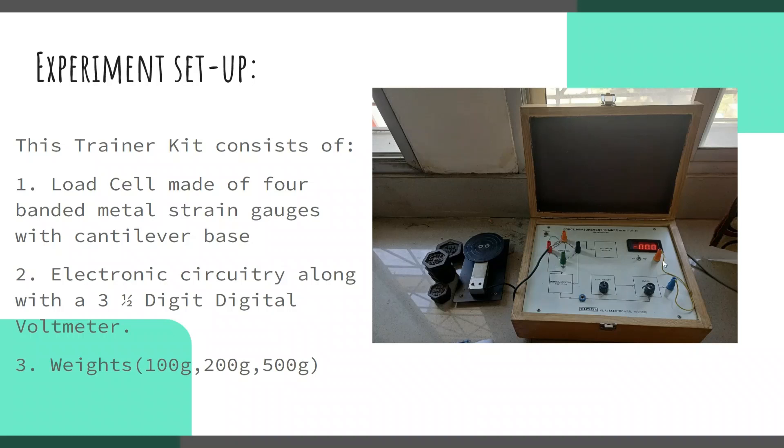Looking into the experimental setup, this is how our force measurement trainer model looks like. This model consists of an internal circuit which is composed of a full configuration Wheatstone bridge where the four arms are connected to the strain gauges that are attached inside the beam. This is a cantilever base and these are the weights. These weights act like force being applied.